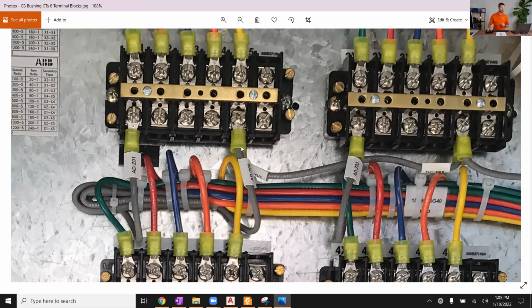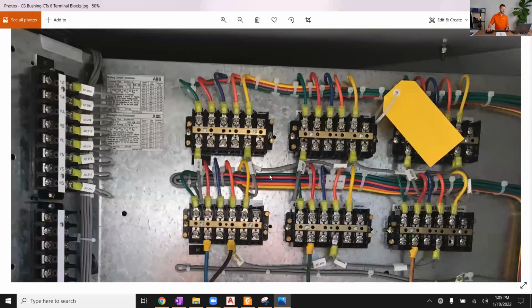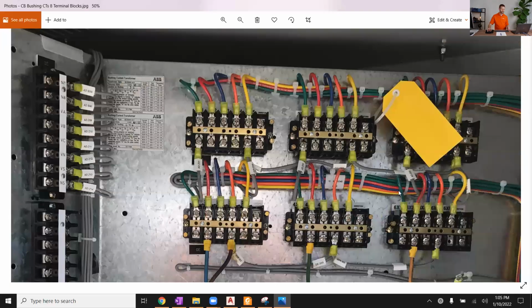You want to make sure that you do have a path to ground in there as well, I believe, from one of those three. Typically, the neutrals are jumpered together and then they go down to the ground. But the key thing is X1 to X5 full tap is where you want to put those shorting screws to make sure that you're not having any open circuit condition. Great point. You can see arcs as well. Not something you want to see.